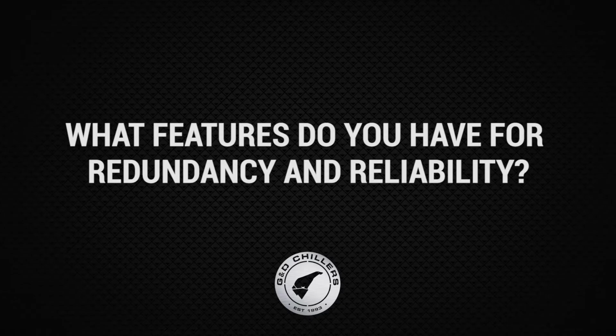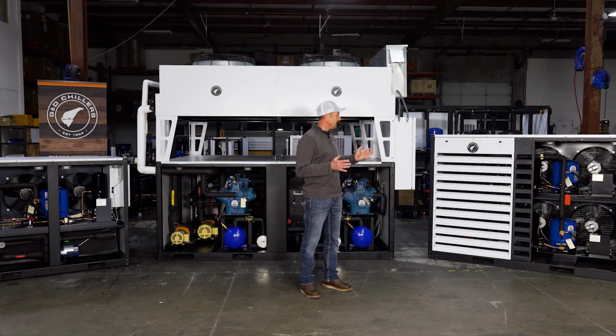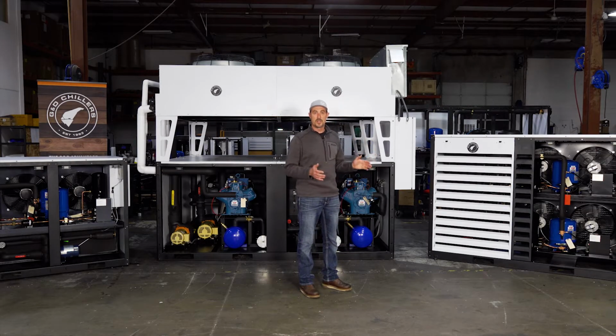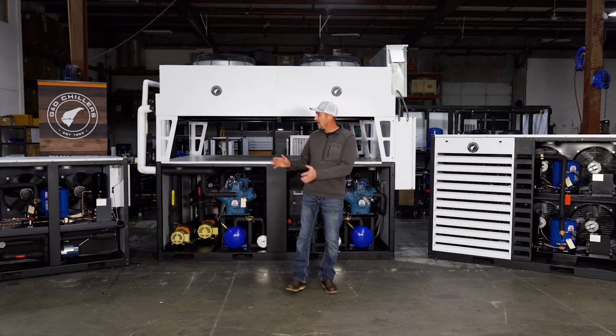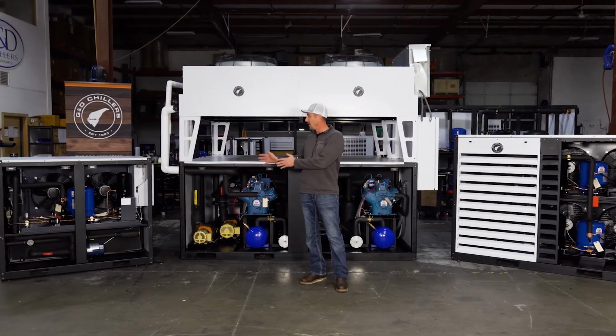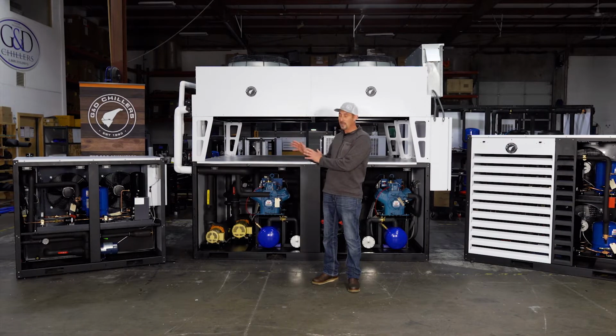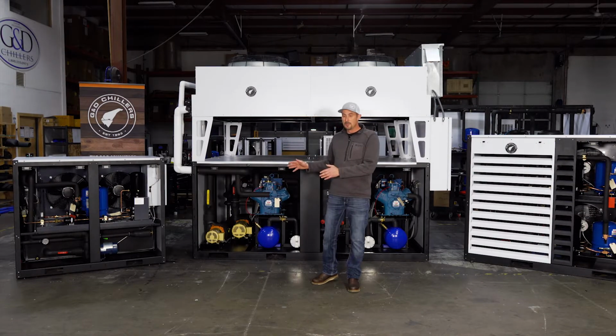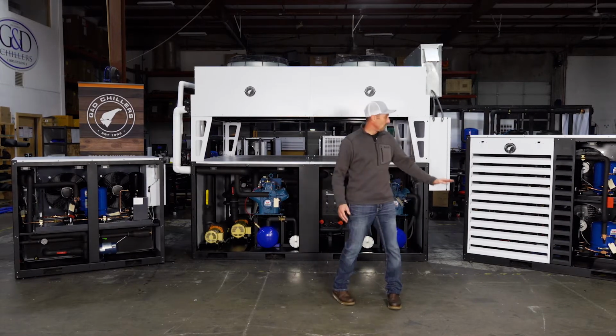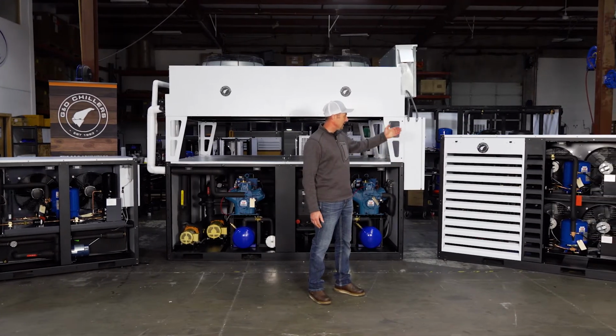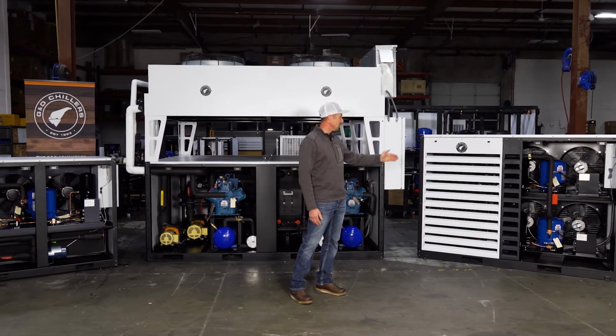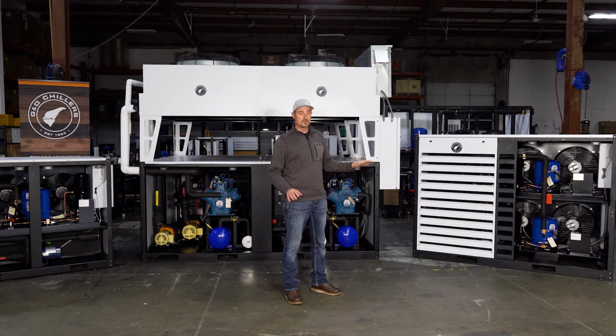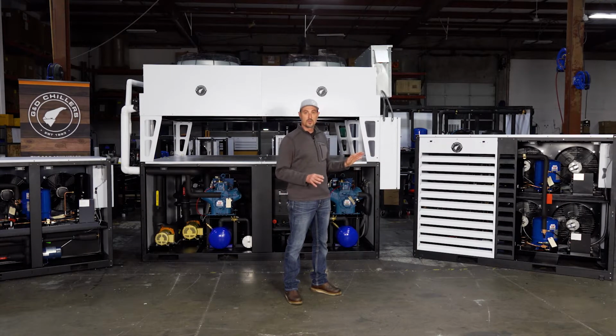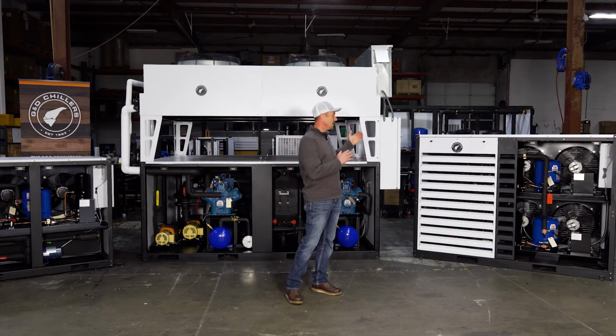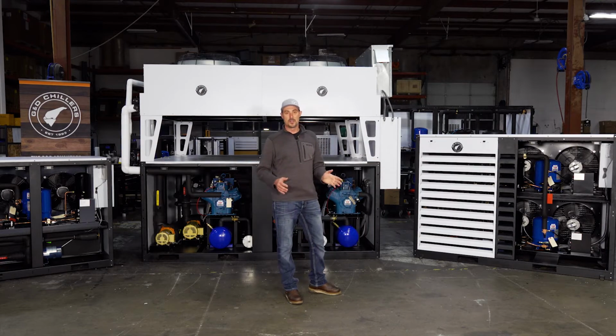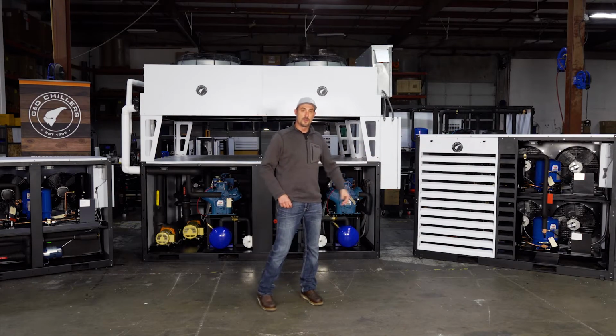If your chiller goes down, you're not making money, so one of the things we really stress is redundancy on all of our brewery chillers. On this smaller scale chiller, we have one compressor, so you don't have that level of redundancy. But with something like this, or even the smaller dual stage chiller, you have redundancy with two compressors that are completely independent of each other, not relied on one another to run. So if something happens with one, you still have 50% redundancy to get you through until the repair can be made.